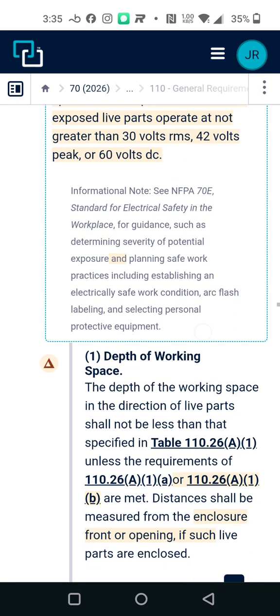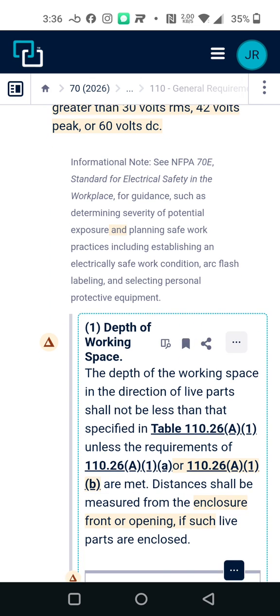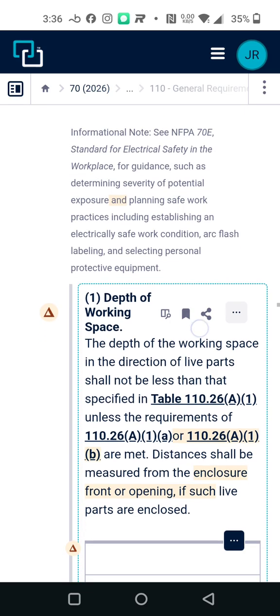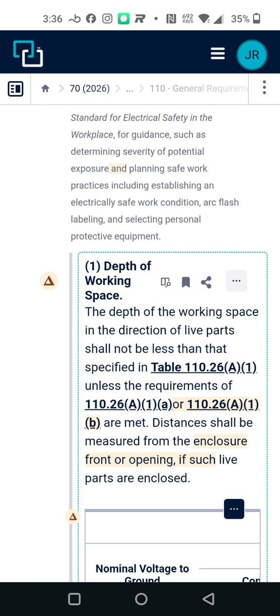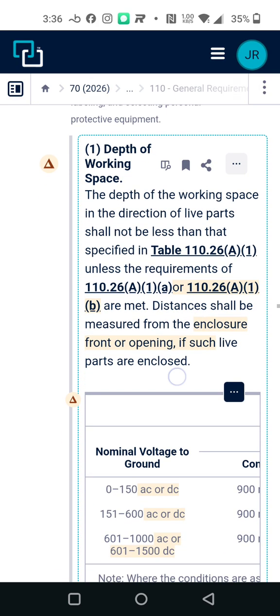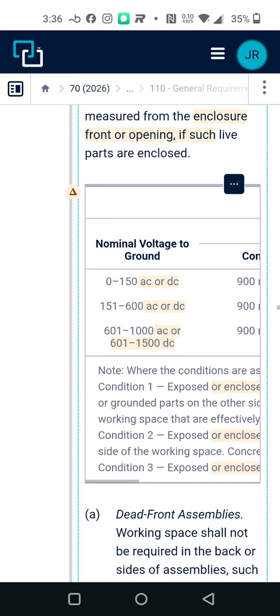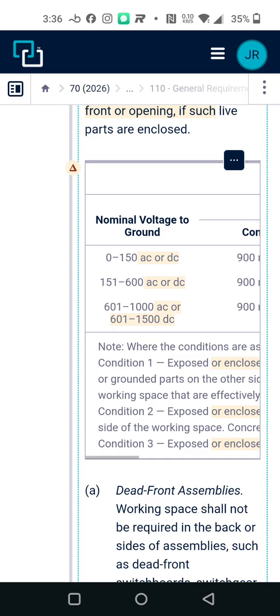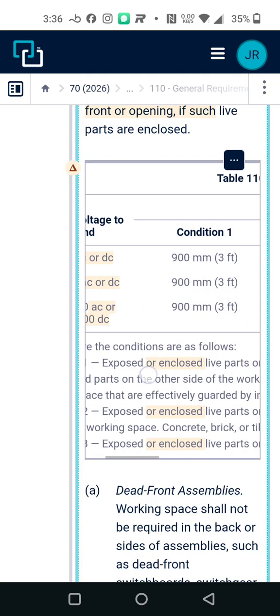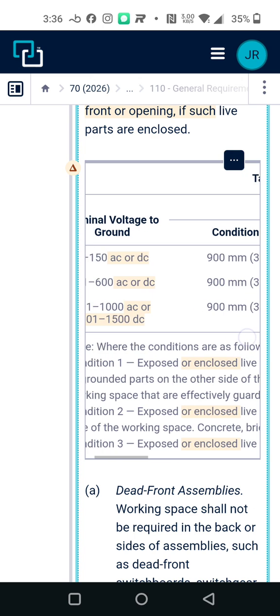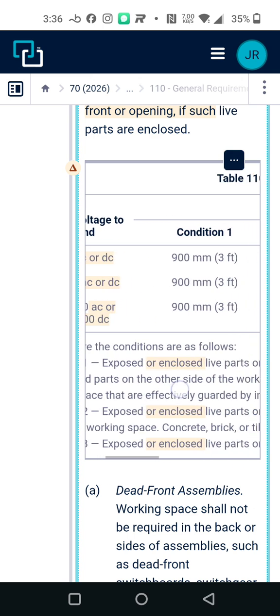Depth of working space. The depth of the working space in the direction of live parts should not be less than that specified in Table 110.26(A)(1) unless the requirements of 110.26(A)(1)(a) or 110.26(A)(1)(b) are met. Distances shall be measured from the enclosure front or opening if such live parts are enclosed. Okay, this is the table for it. Nominal voltage to ground, 0 to 150 AC or DC, it's 900 millimeters, condition 1. You see what condition 1 is down here.